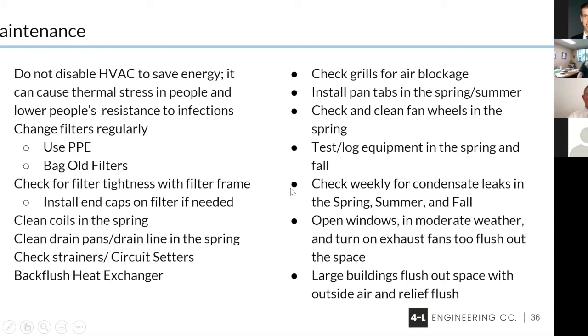Check for condensate leaks. One of the things that we need to be concerned about: if we develop condensate leaks and they start to drip down into areas in our ceiling or on the floor, remember that that creates mold. So when the mold triangle comes into play, that's where we have food, moisture, and air. Air, we can't control what's around us. Moisture is coming because of the leak. Dirt is any surface or materials that may be there. So the thing to do is to control the moisture. Open the windows in moderate weather, flush it out with your exhaust fans. In large buildings, normally commercial buildings, we'll recommend that they open their outside air dampers and flush the building out with 100% outside air. Slide.